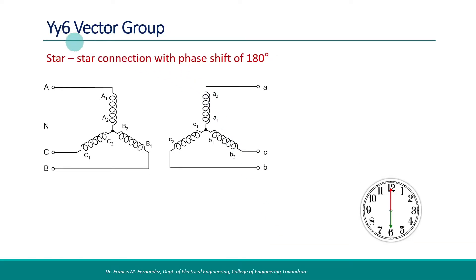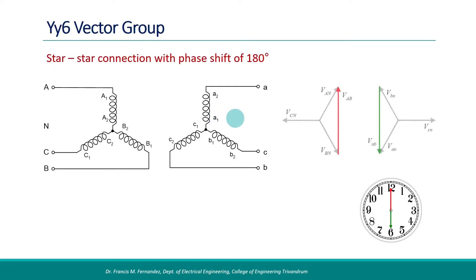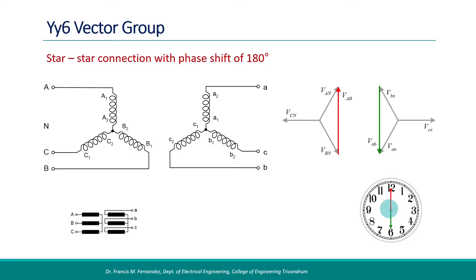Next is the YY6 group. Both the primary and secondary windings are star connected, but the polarity of each winding is reversed in the secondary side — on the primary side it is A1, A2, and on the secondary side it is A2, A1. This reversal of polarity is done in other windings as well. This results in a 180-degree phase shift in voltages in the secondary, represented by the clock hand positions at the 6 o'clock position. The simplified connection diagram and the displacement diagram are shown.